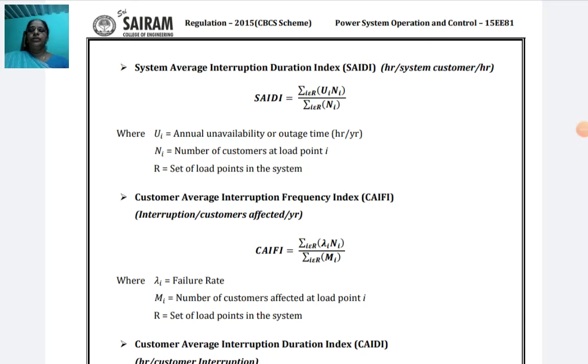Dear student, now I will give a lecture on the continuation of adequacy indices at hierarchical level 3. The parameter is the system average interruption duration index, SAIDI. The formula: the numerator is the summation over i in r of Ui Ni, the denominator is the summation over i in r of Ni, where Ui is the annual unavailability or outage time, and Ni is the number of customers at load point i or set of load points in the system.